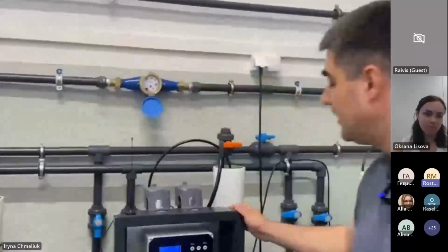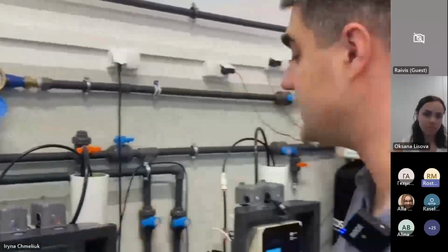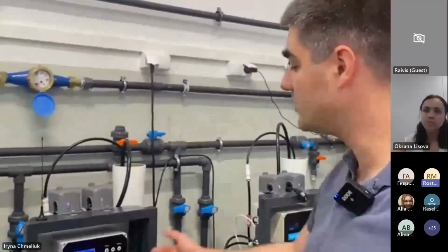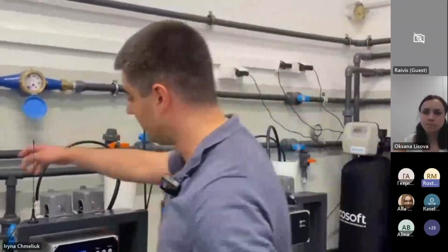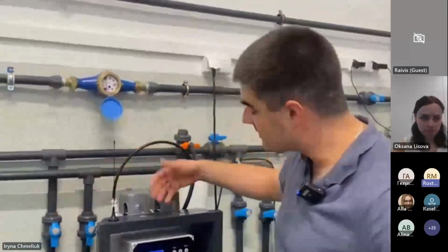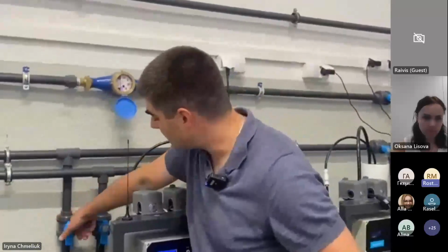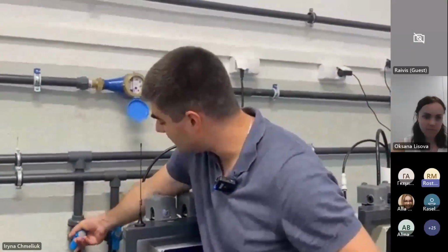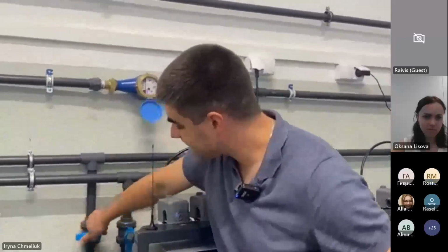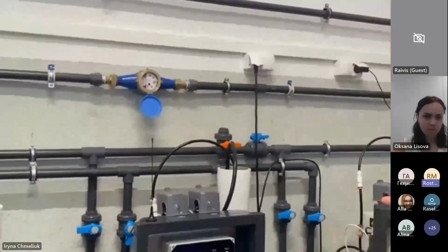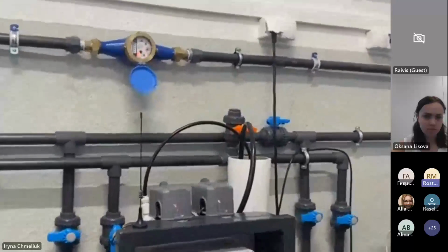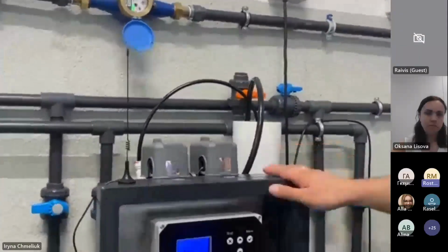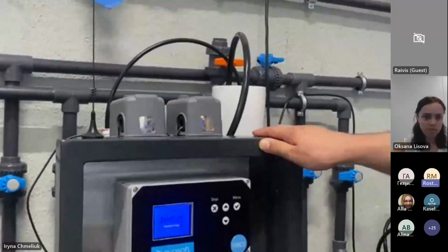So on the alarms, let's see what we do with the alarms. As we already saw about 10 minutes ago, the most popular alarm is the no water. So now the system is operating, and I will just close the water before the unit. I believe you have heard the relay. And now the system would stop.